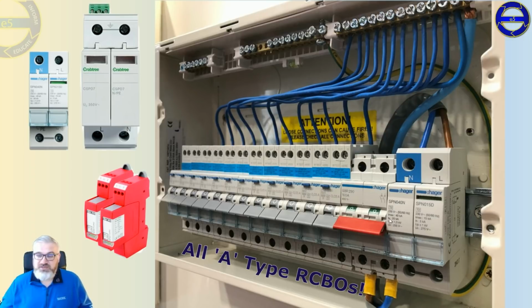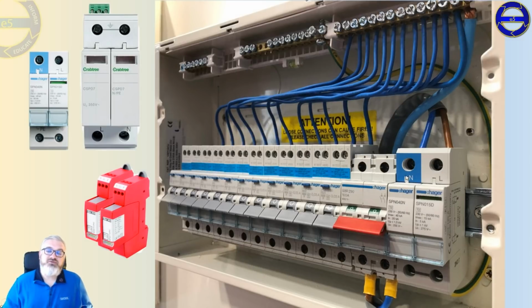Now with this board, something different is these parts here on the far right, which is the surge protection devices. You can see it here clearer. Crabtree have their own version, and Proteus and Chint and many other companies do. Now all this does is it takes a live and neutral from the bottom of the outgoing of the main switch into the top, and what that's supposed to do is any overvoltage or transients that would spike on that mains, it effectively would go through this device. This device would then safely discharge, recognise it and discharge via a 16mm CPC to the earth bar and away.